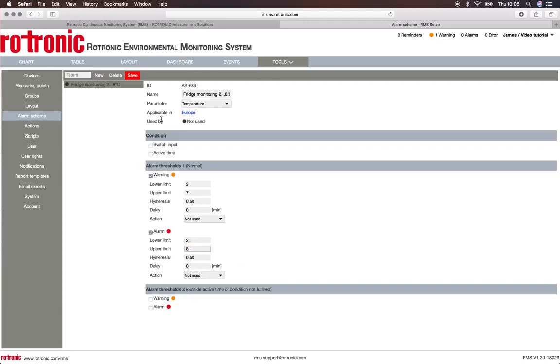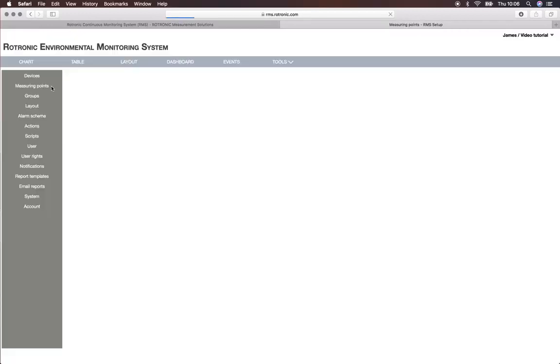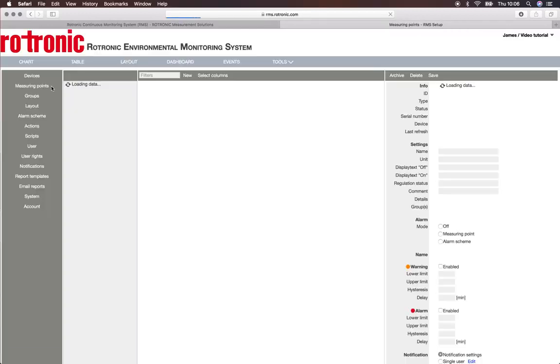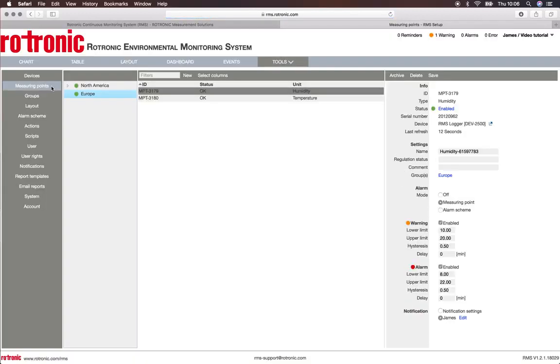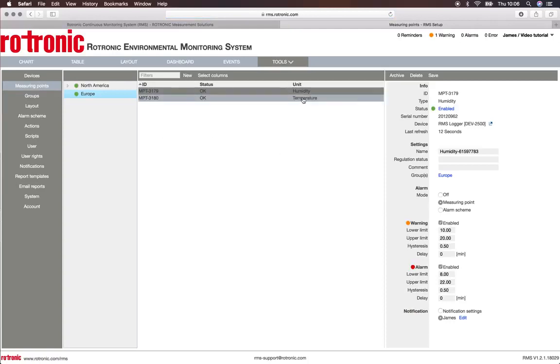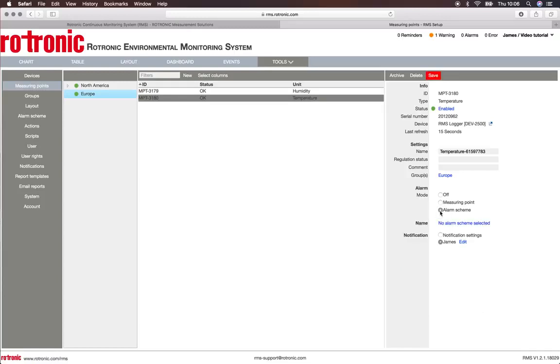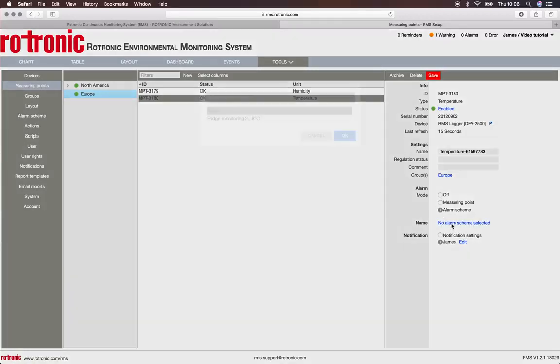I can now click on Save and I have saved this alarm scheme. If I now go to measurement points, as we were talking about temperature, I go to the temperature measurement points. I now have the possibility under Alarm to set the alarm scheme. I click on Alarm Scheme, I choose the name, and I have my fridge monitoring 2 to 8 degrees Celsius. I click on OK.